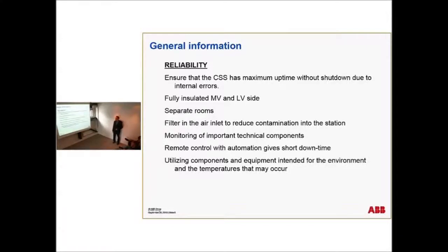Reliability. Ensure that the CSS has maximum uptime without any shutdown due to internal errors. Fully insulated low voltage and medium voltage side, of course. We have separate rooms or separate spaces for the 2 different apparatus. Filters are very important, at least in the north of Norway and Iceland as well, in the ventilation because of the contamination inside the station. Snow and so on. Monitoring of important technical components. That's of course very important as well.